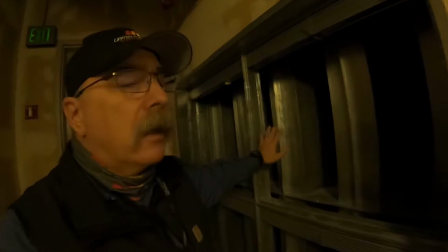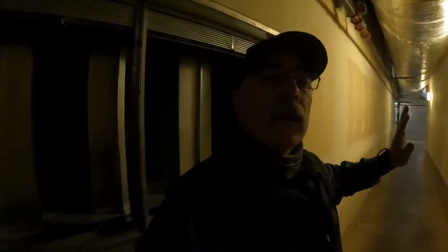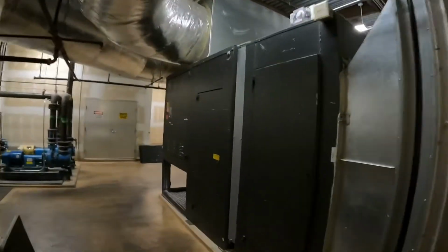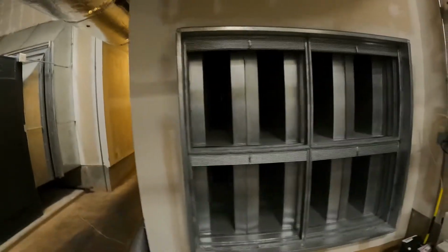So my air in this building comes from above the ceiling tile on all the floors into this big giant return here. It's just wild. There's no ductwork connected to it. There's just grills in the ceiling pulling the air up, bringing it in this big giant chase and bringing it into this mechanical room.